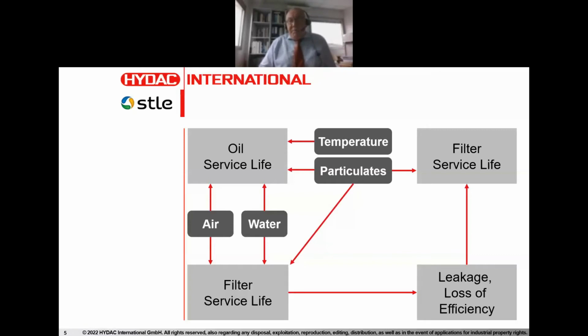Also, in terms of how it affects the oil service life or component service life, it matters whether it is free water or dissolved water, so the saturation limit here plays a big role. And again, this has an impact on filter service life, because if you now generate a lot of chemical contaminants that derive from chemical breakdown, the filter service life is going to decrease very often quite dramatically.